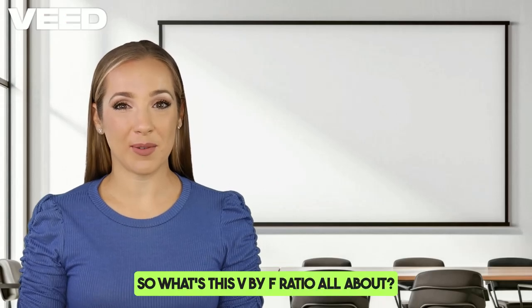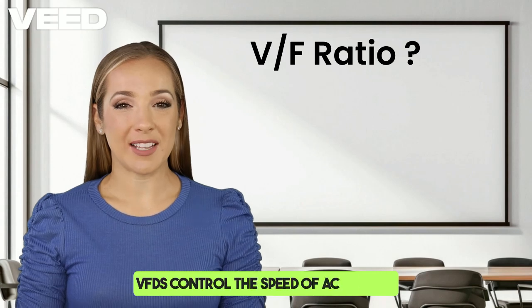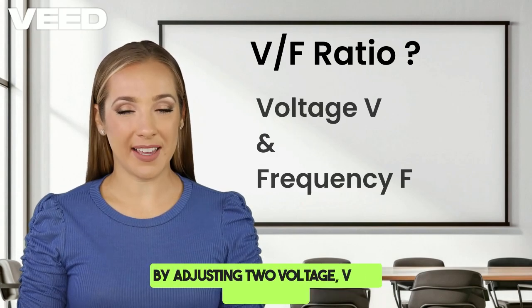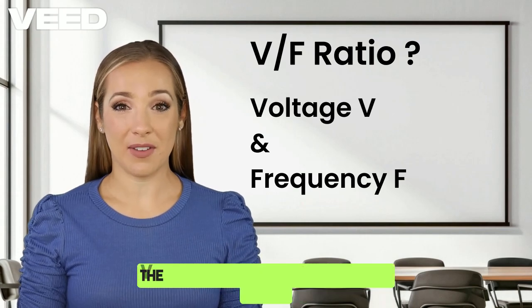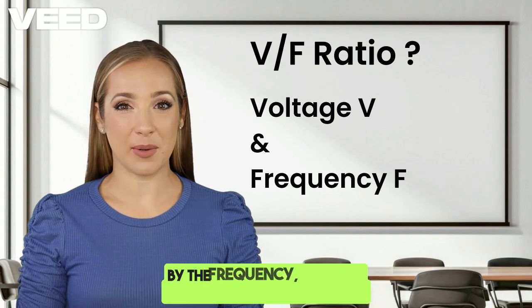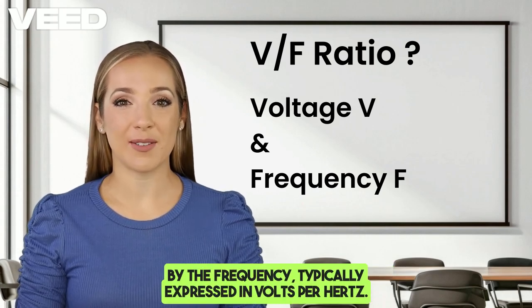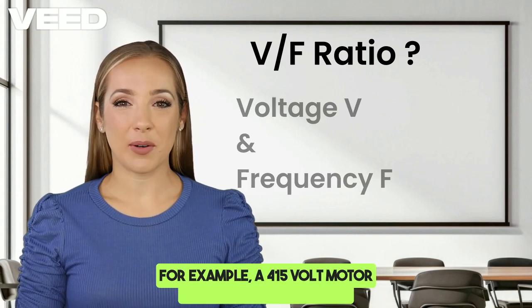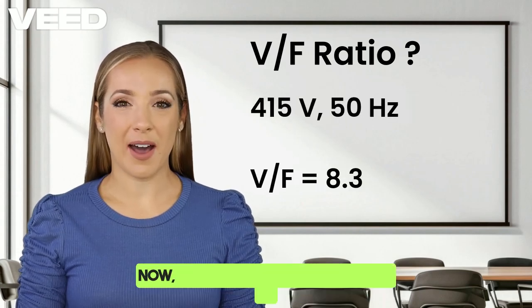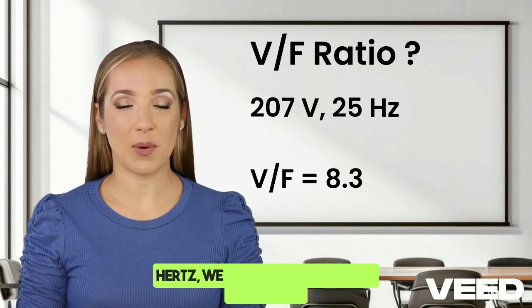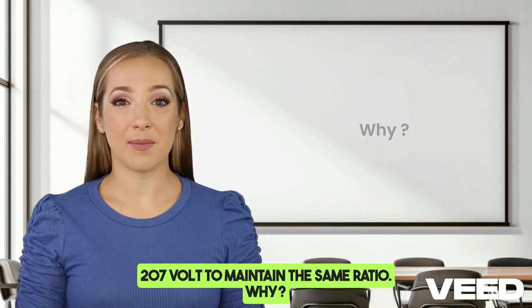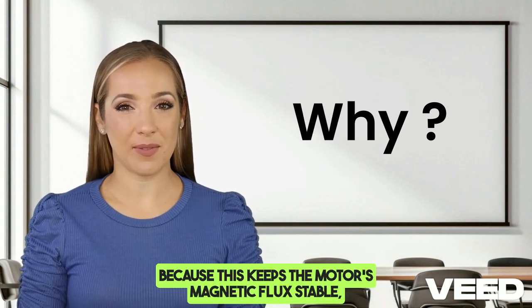Let's get started. So, what's this V by F ratio all about? VFDs control the speed of AC motors by adjusting two things: voltage, V, and frequency, F. The V by F ratio is simply the voltage divided by the frequency, typically expressed in volts per hertz. For example, a 415-volt motor running at 50 hertz has a V by F ratio of 8.3 volts per hertz. Now, if we reduce the frequency to 25 hertz, we must also reduce the voltage to 207 volts to maintain the same ratio. Why? Because this keeps the motor's magnetic flux stable, preventing issues like overheating or torque loss.